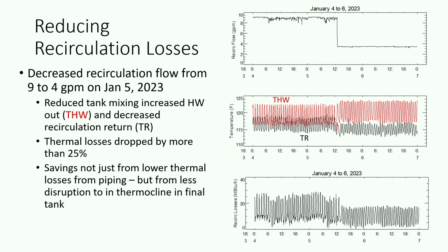So we had this nice experimental setup, so we thought, well, let's lower the recirculation flow rate and see what happens. And so at the beginning of January 2023, we lowered the recirculation flow rate back from the building from 9 GPM to 4 GPM. And of course, how do you choose the GPM? Whatever pump is cheapest at the supply store, I think, is how you size it. Of the 6 multifamily buildings we've measured, it's always 8 to 15 GPM. And really, it only has to be high enough that the recirculation temperature coming back is 110 or 115, and that's how you can be pretty sure you have hot water to every fixture, even on the end of the line.